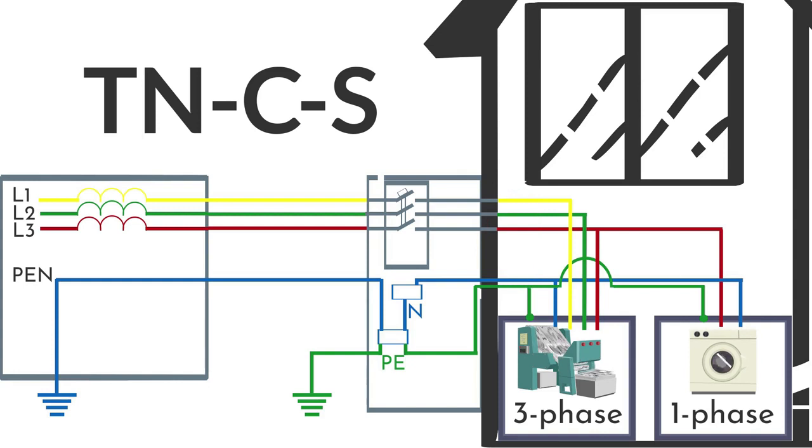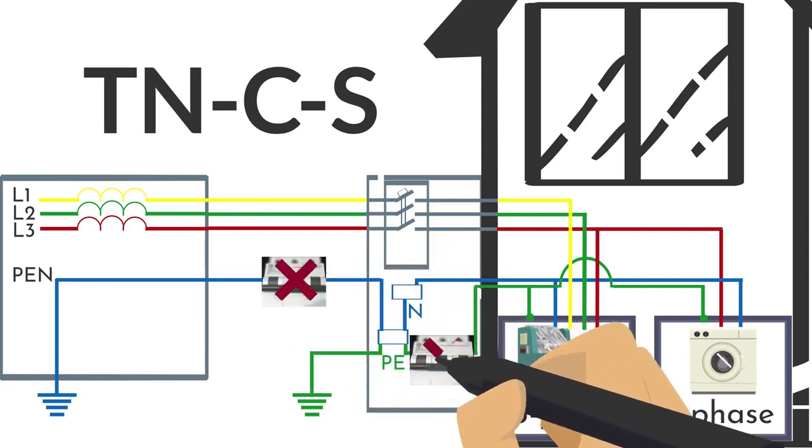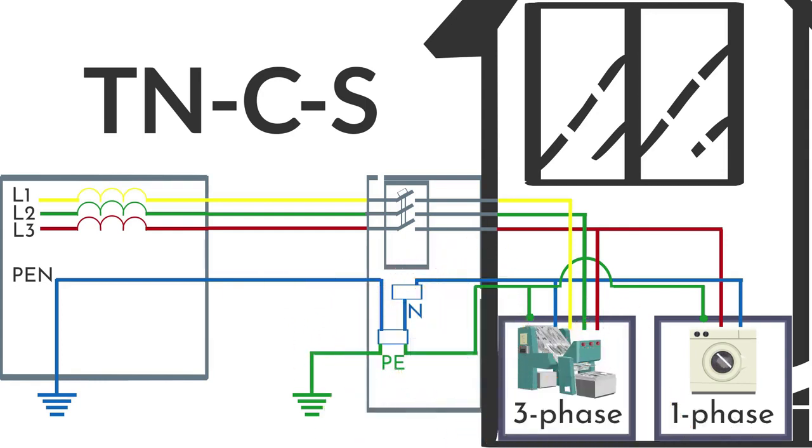In case of a single phase circuit, three wires, namely phase, N, and PE conductors, come into the house after dividing the PEN conductor into N and PE elements. It is strictly forbidden to connect them inside the house. Moreover, PEN and PE conductors must not be broken by any automatic circuit breakers. You can only break the N conductor circuit.